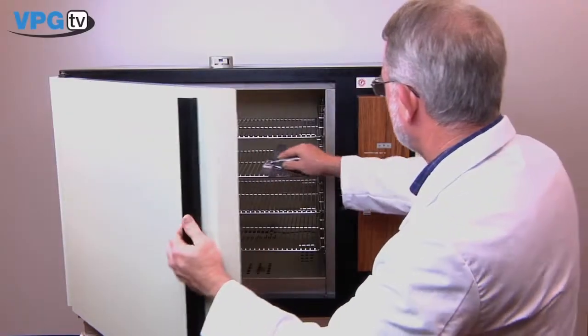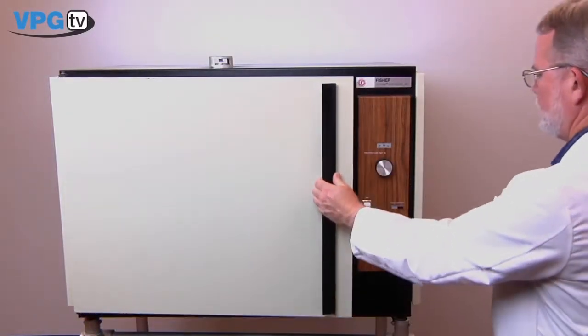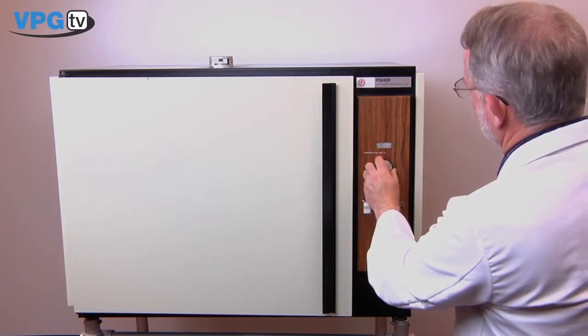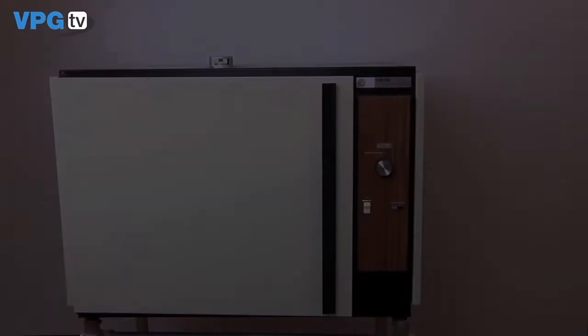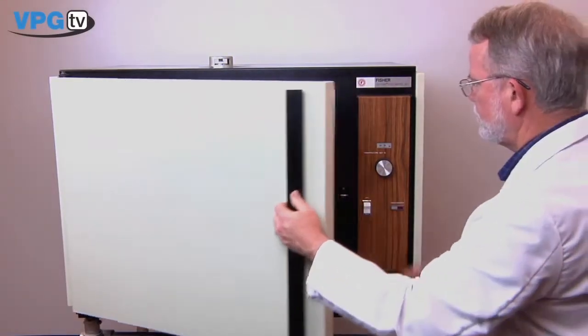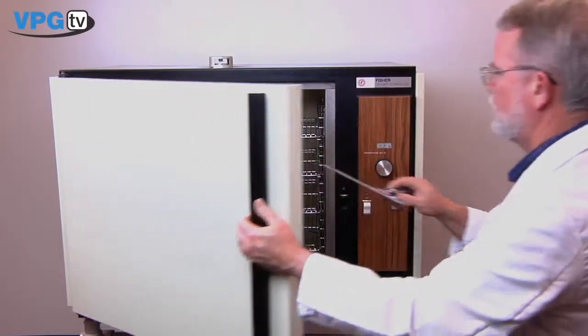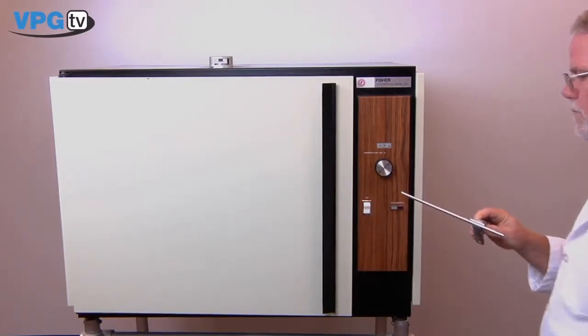Place the clamped gauge specimen into a cool oven and raise the temperature to the desired level at a ramp rate of between 5 and 20 degrees Fahrenheit per minute. The recommended time versus temperature curves can be found in our instruction bulletin B130, provided with each M-Bond 610 kit.